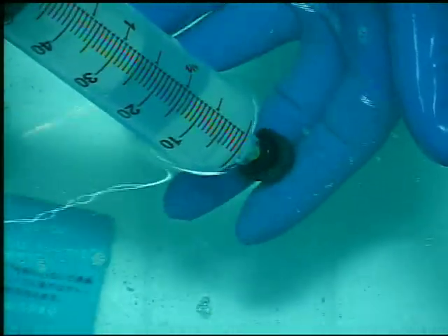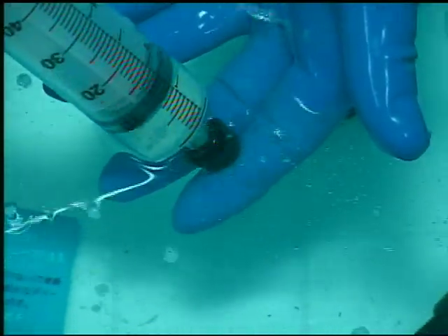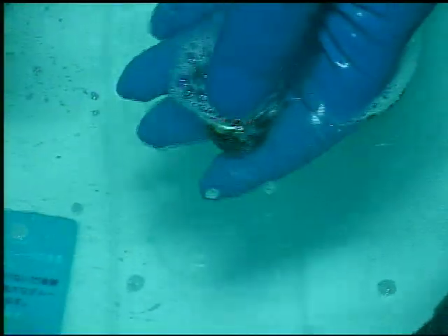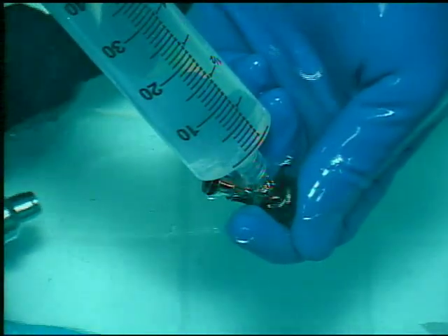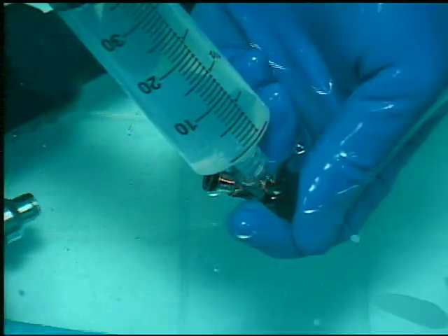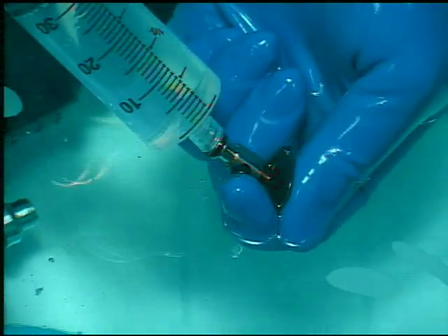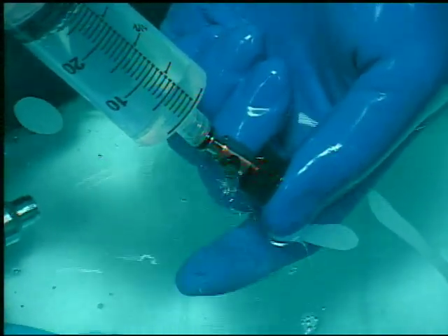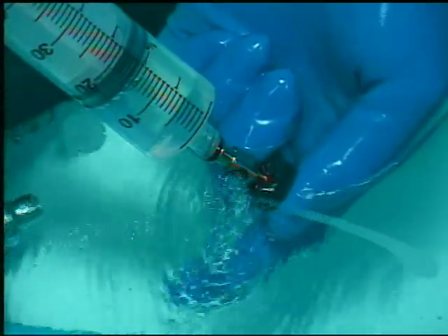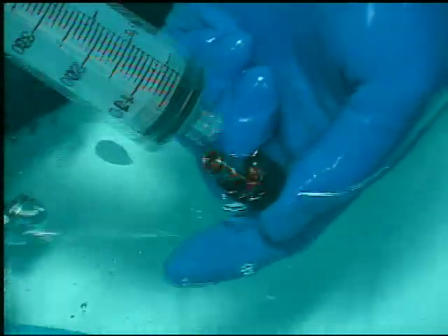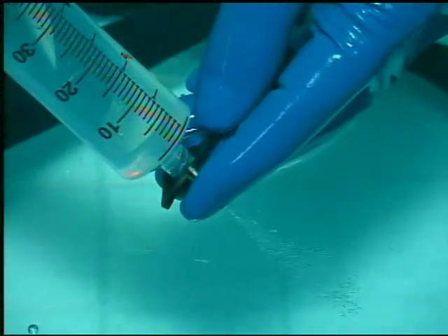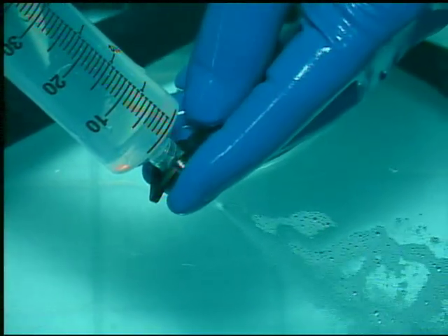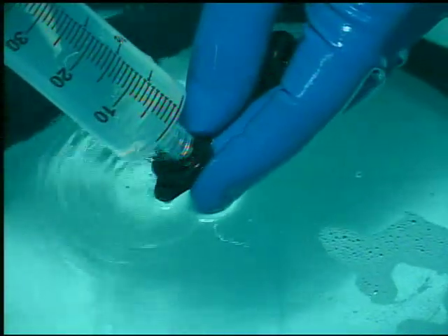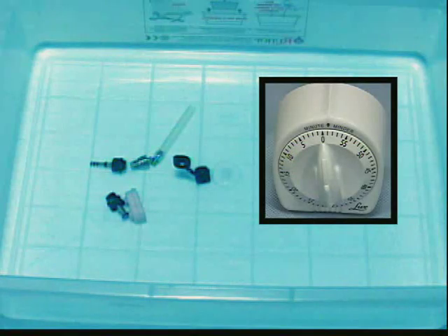While fully immersed, manipulate valve mechanisms and use a syringe to inject disinfectant through or into removable scope components. This will remove entrapped air bubbles that could inhibit contact of solution with component surfaces and provide for better exposure of surfaces to germicide. Make sure disinfectant is injected into or through the rubber inlet seal. The endoscope component parts should remain in contact with the disinfecting solution for the time period recommended by the manufacturer of the solution.